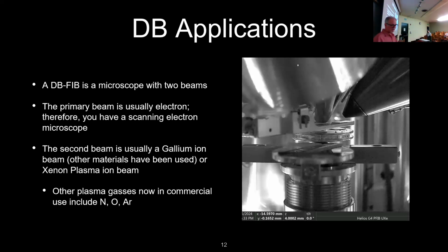So, dual beam FIB application. Dual beam means that we have two beams. The primary beam is typically an electron beam. The secondary beam is an ion beam. More often than not, that second beam is gallium. Plasma is coming into its own these days, but there are other gases for the plasma side and other metals for the liquid ion metal side. People have used bismuth.